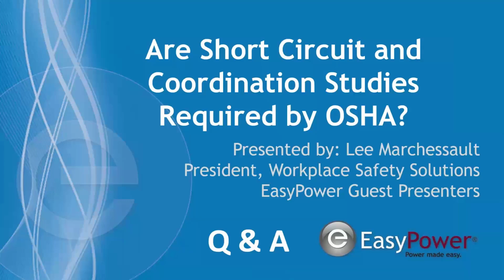So if you are sure the arc flash level is at very low levels, say a panel at less than 1.2 calories, the likelihood of having a higher level is unlikely unless you have a large motor load or long runs of wire. But most of the time, downstream will be at that same low level or lower, because you're now two levels of protection down beyond the low level that you already have.